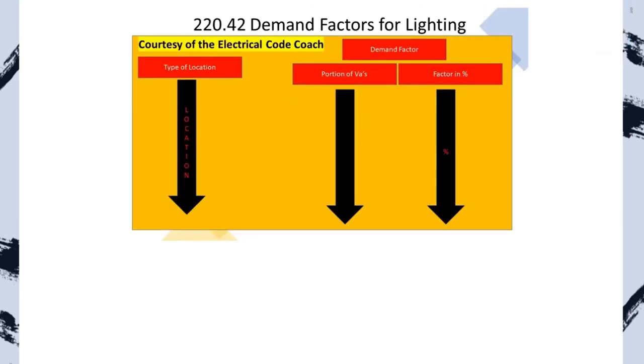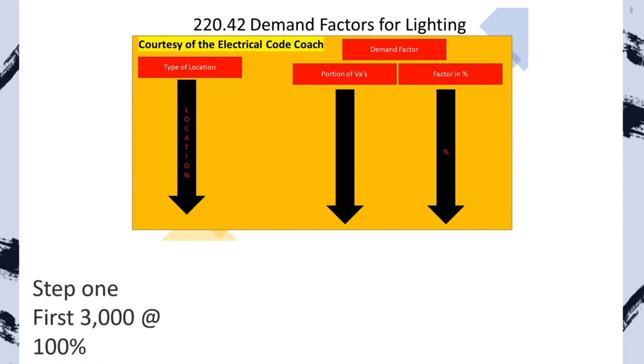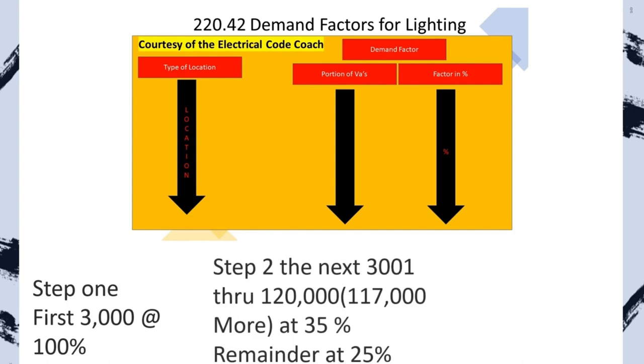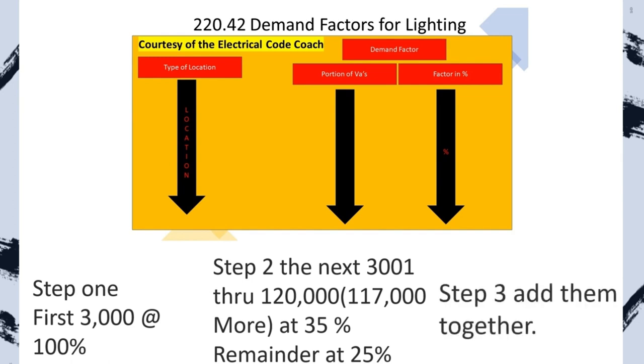For dwelling units, Table 220.42 has a multi-layered demand factor. Step one: take the first 3,000 VAs at 100%. Step two: take the portion between 3,001 and 120,000 — essentially the next 117,000 VAs — at 35%. Then take anything above and beyond that at 25%. Step three: add them back together. We take the original 3,000 we set aside, then add the new reduced load to get our total.